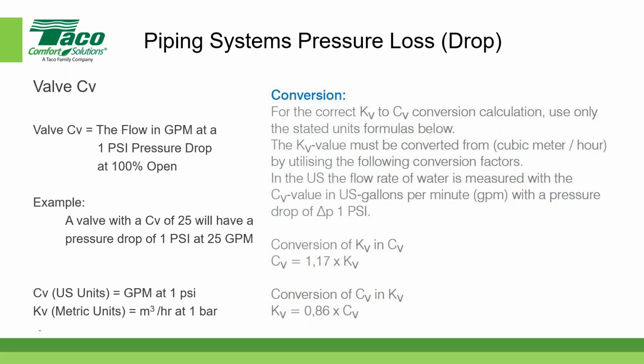Yeah, and most of the time, when it comes to generic valves like ball valves and things like that, they generally don't publish the CV value, or they'll just give you the pressure drop. Most of the time, manufacturers publish the CV value for control valves, or zone valves, or things like that. Something electronic, more, yeah. Generally speaking, something that has some kind of control function.